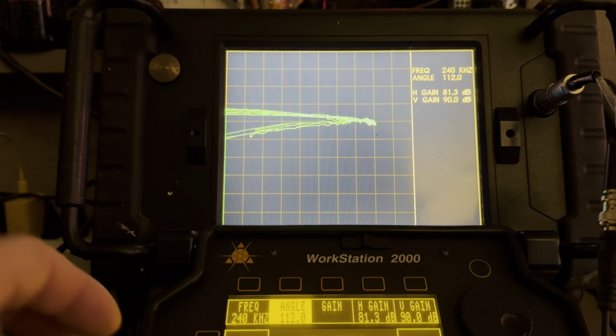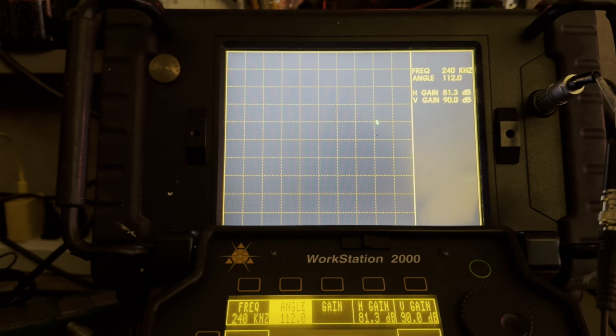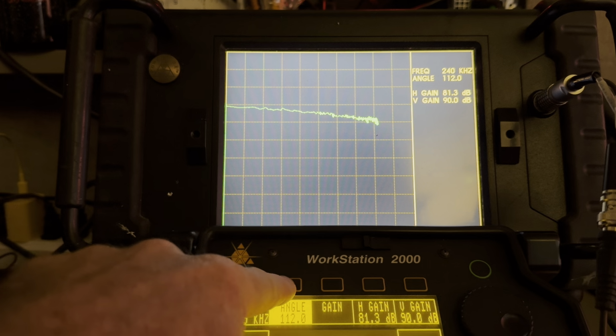All right, so we're tapping away. A good test is you always want the operating point for your material to be on the right and have liftoff vectoring to the left. So right now my coil is in air, and as I bring it down to the test material, the operating point is going to the left. So that's 180 out. So I'm going to use my angle control.